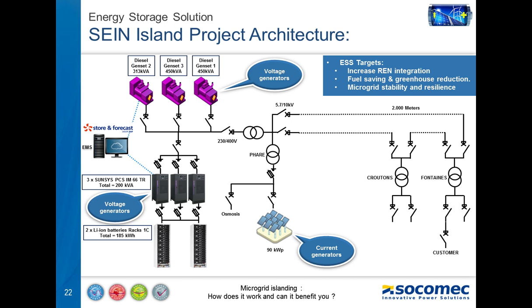In the first step of this project, like you said, Etienne, 90 kilowatt peak of PV were installed and combined with an energy storage of about 200 kVA and 185 kilowatt hour. The sizing of the energy storage solution was based on the fact that in some new steps coming in the future years, the total planned PV production could reach 150 kilowatt peak.